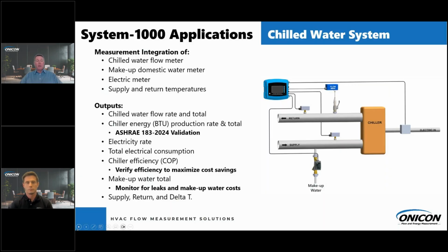As a side note, if you're someone who's working through an ASHRAE 183 validation, the data that you're getting for that chiller BTU production can help you with your ASHRAE 183 validation. Using the electric meter on the right of the diagram, you can bring in your electric rate and your total electrical consumption. And once we have that in our BTUs, we can do a chiller efficiency calculation for a COP. That's really great if you're trying to verify the efficiency of your equipment or you're looking to maximize your cost savings.